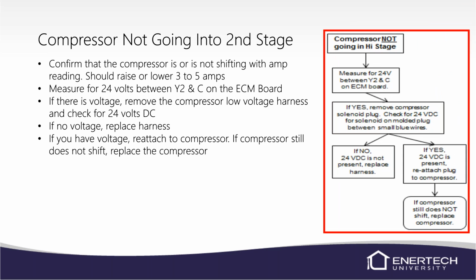We also have the compressor not shifting. If the compressor is running but just not shifting, we can confirm that with amp draw. It should raise 3 to 5 amps, or about 33% of the total amp draw. You can also make sure we've got voltage to Y2. So measure between common and Y2. You can measure it on the ECM board. It comes from the thermostat terminal strip and goes to the ECM board and then leaves there and goes to the different components, lockout board, things like that. So you can check it at the ECM board on those little screw terminals. It'd be close to 24 volts.